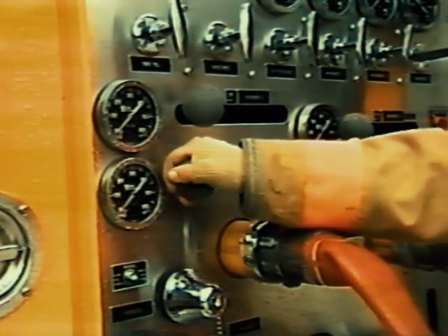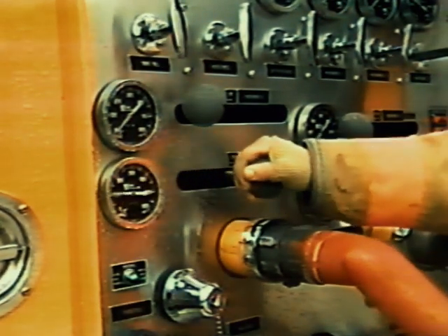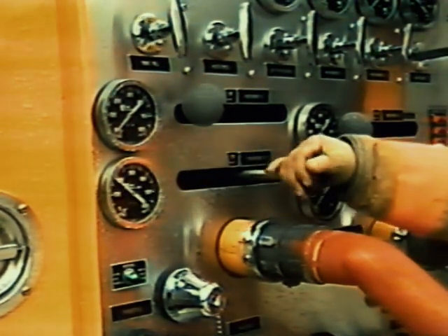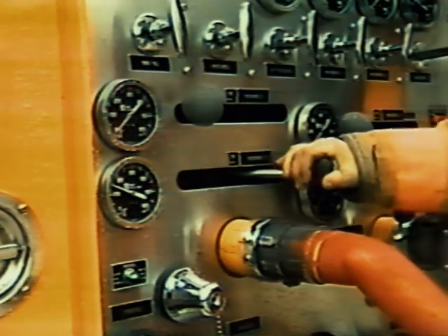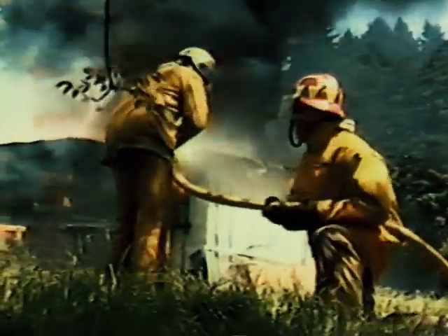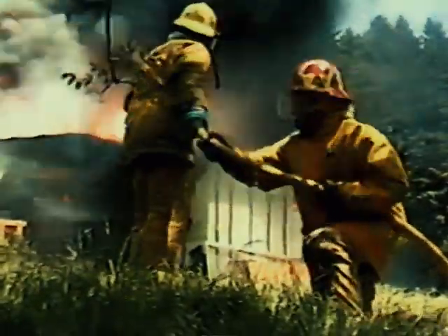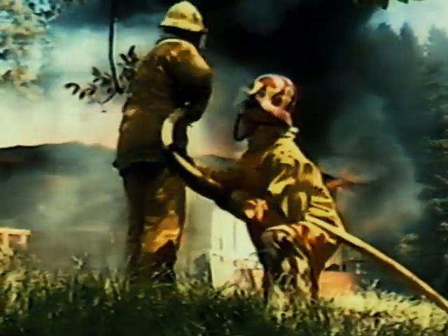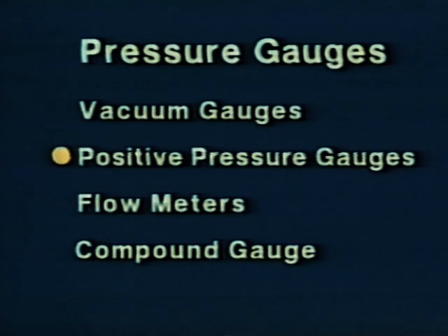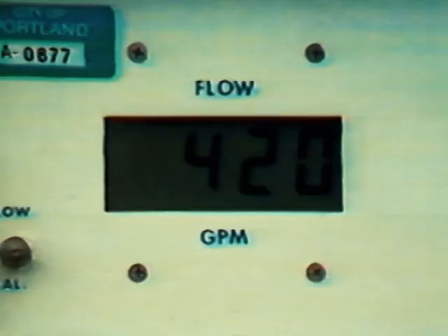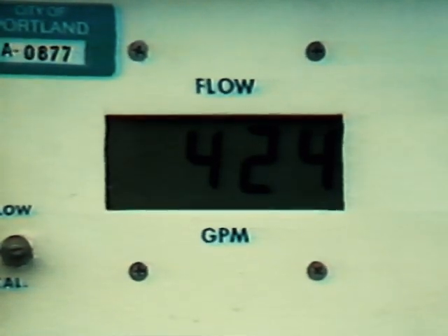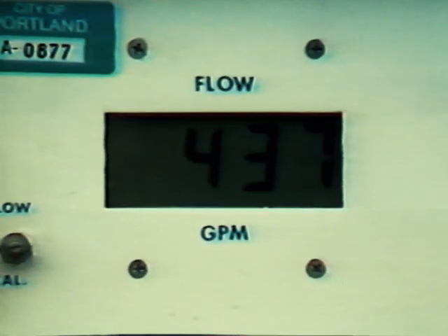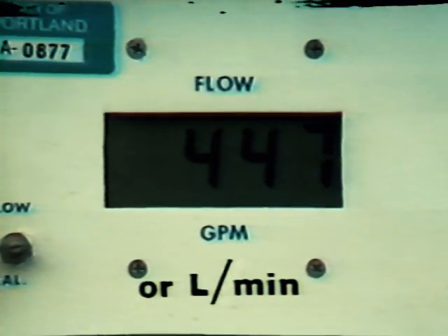Having individual gauges at each discharge gate allows you to adjust the gates to supply each hose line with the optimum pressure, to increase operating efficiency and greater safety for the nozzle operators. Many fire pumpers use flow meters instead of positive pressure gauges at each discharge gate.